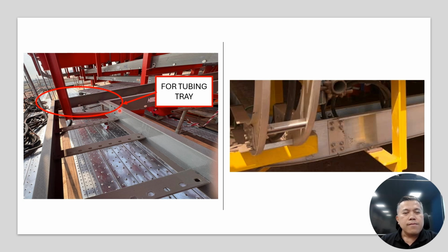Okay, that's why you can see there is no 45 degrees, there is no slope. Like when you bend the cable, this is the problem. There is no bending of your cable. It's a sharp bend, so that is not acceptable for the cable tray if you are installing for cable installation.